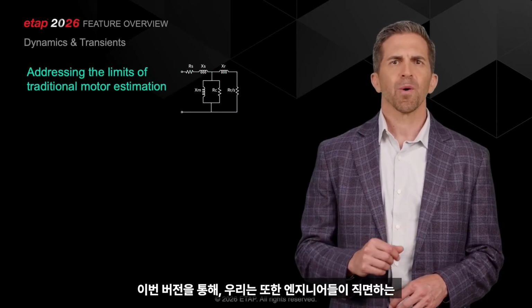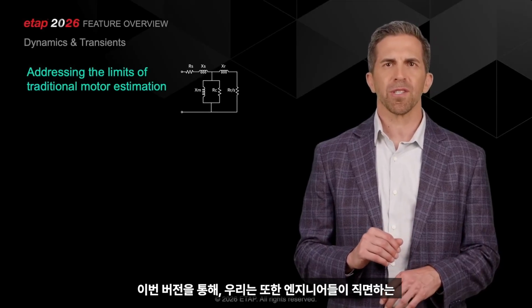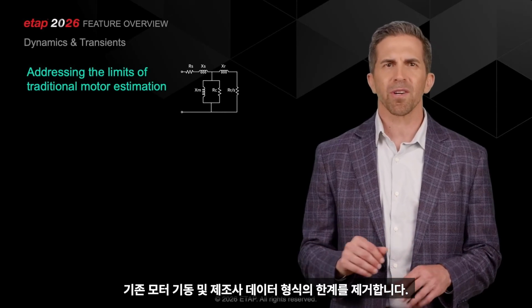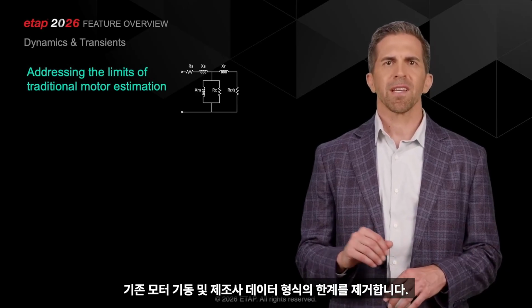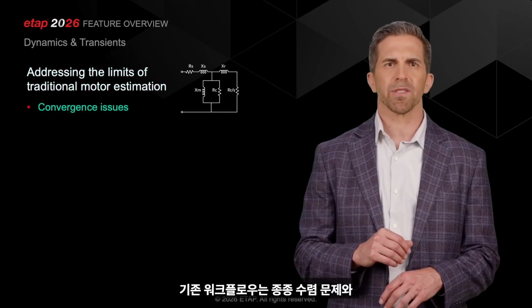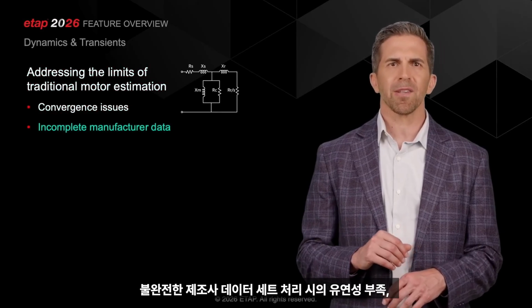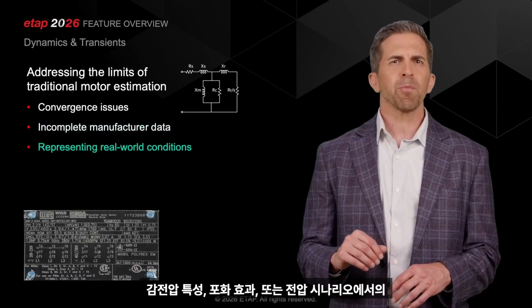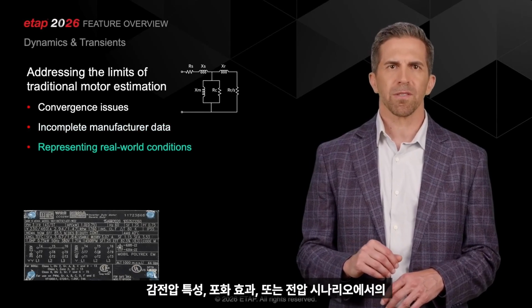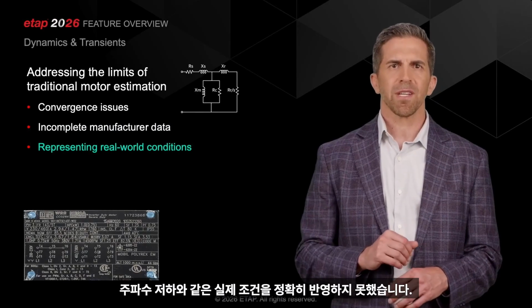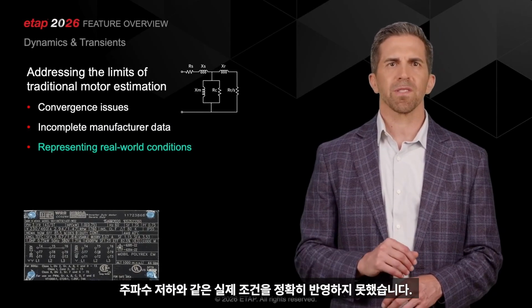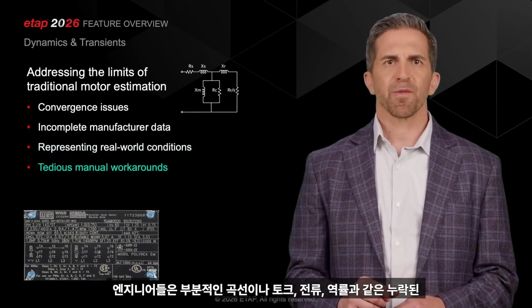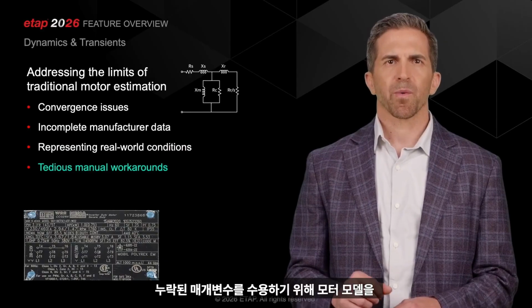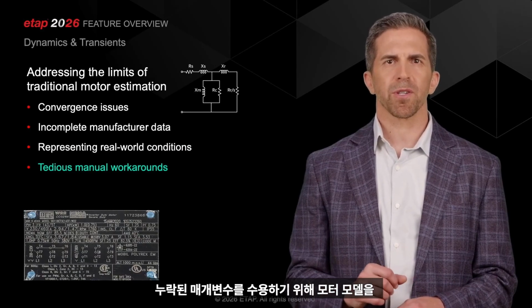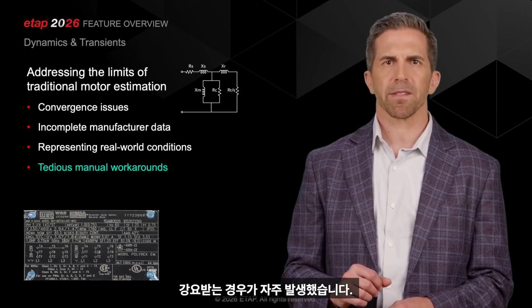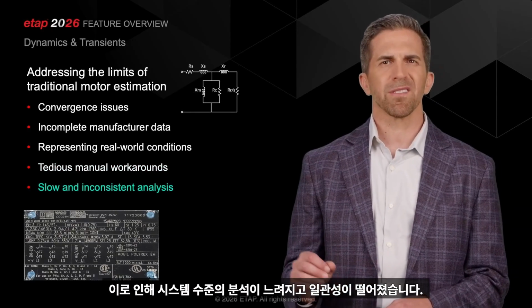With this version, we also set out to remove the fundamental limitations engineers face when relying on traditional motor starting and manufacturer data formats. Conventional workflows often struggle with convergence issues, limited flexibility in handling incomplete manufacturer datasets, and the inability to accurately represent real-world conditions, such as reduced voltage characteristics, saturation effects, or degraded frequency and voltage scenarios. Engineers are frequently forced into manual workarounds, redefining motor models just to accommodate partial curves or missing parameters like torque, current, or power factor, making true system-level analysis slow and inconsistent.